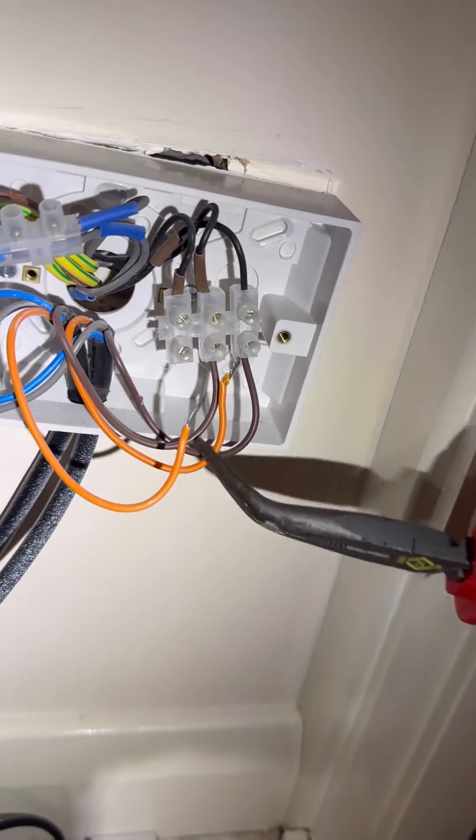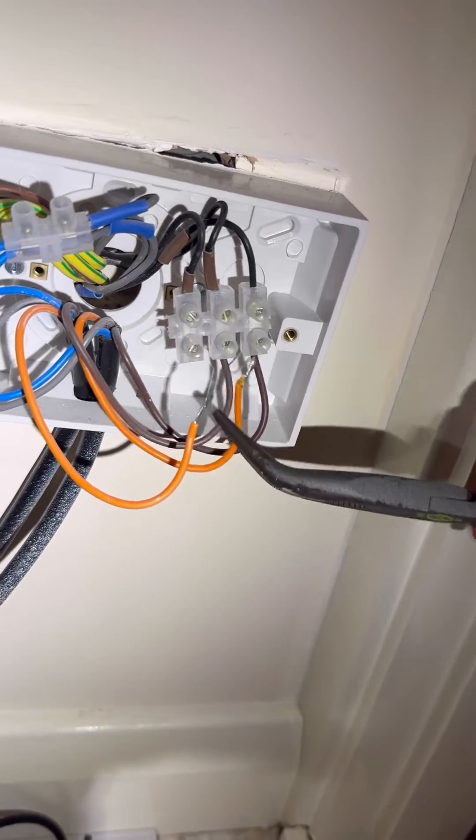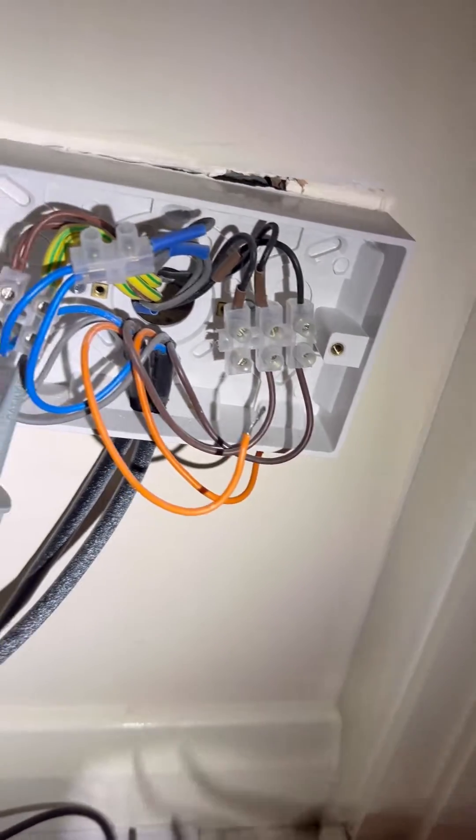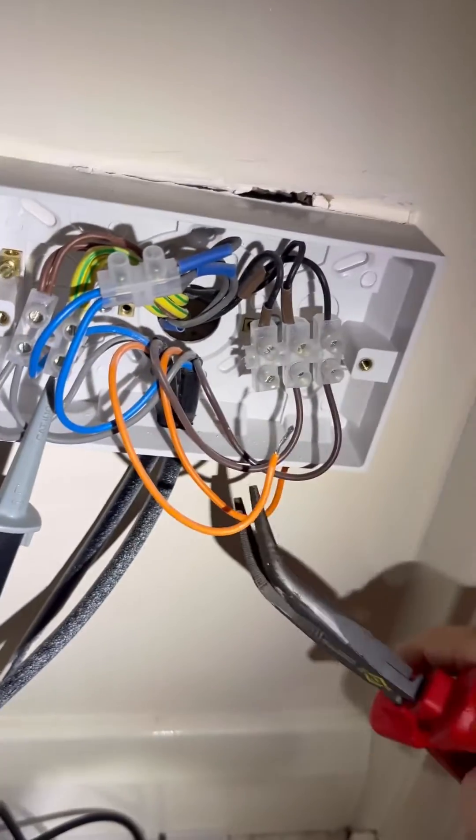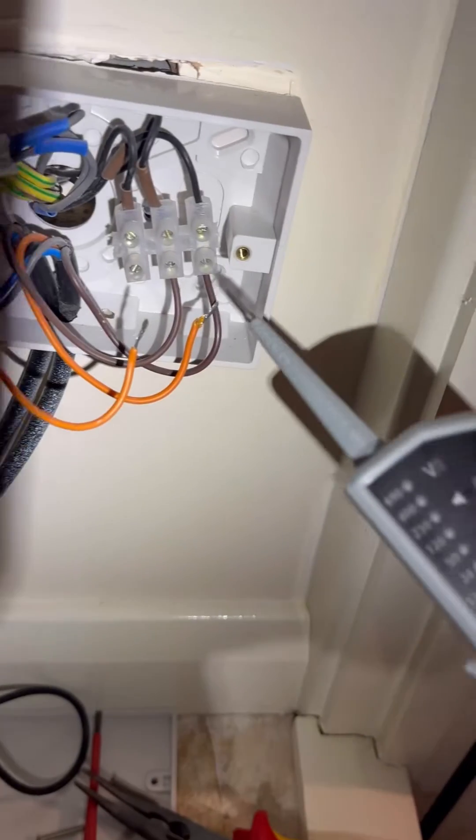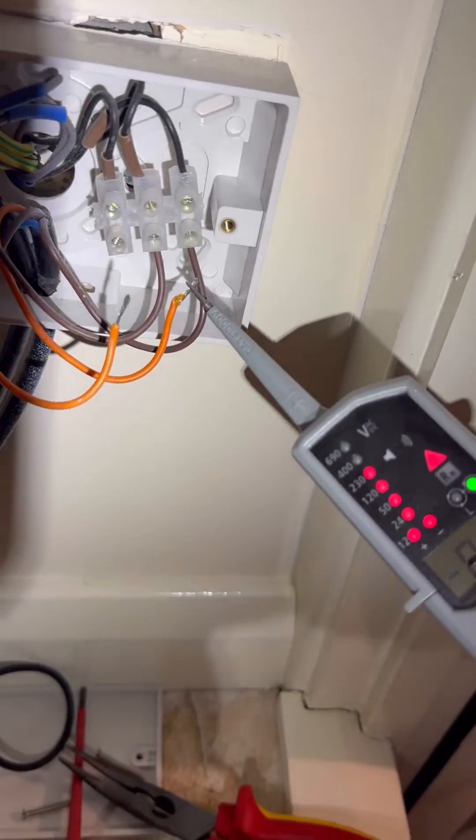So the left is the zone valve for upstairs, right is the zone valve for downstairs, which is where they were saying the heating was constantly on. The terminal that it went in, that would be a switch live back down to the boiler. So it could be coming from either valve or the boiler. So this little test determines it.